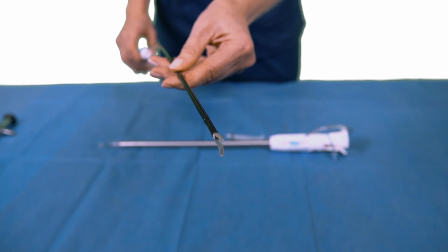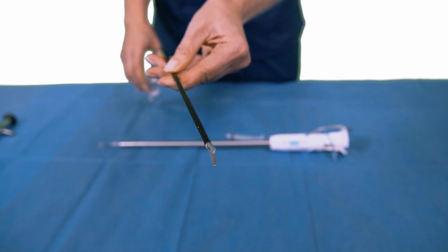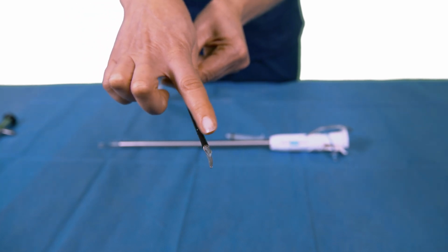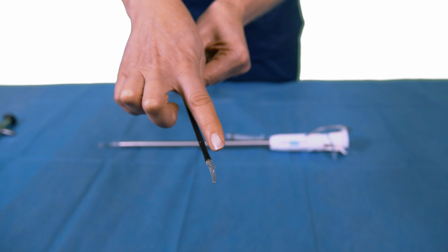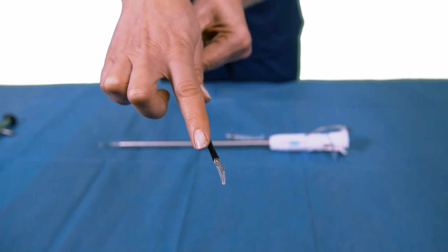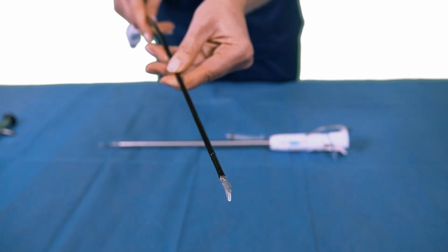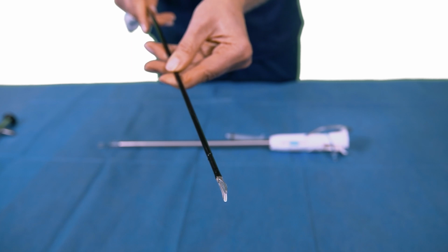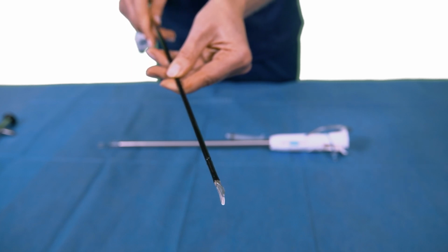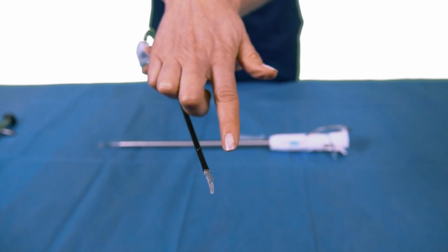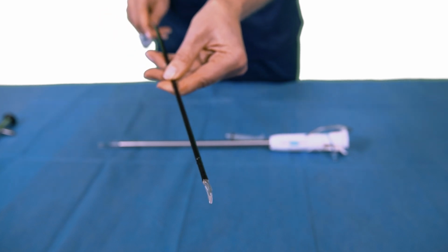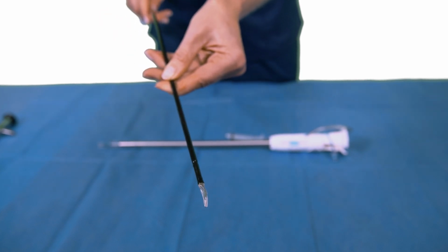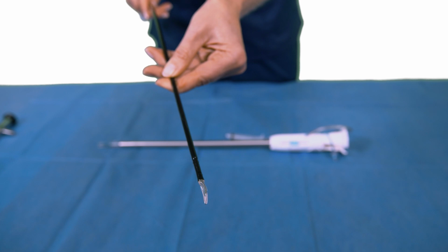The Hemopro cutting jaws have a concave side and a convex side. The concave side is the side with maximum insulation, and that's the side that should be facing the main vessel. On the convex side is a spot cautery, which can get hot with activation, and that should be facing away from the main conduit.